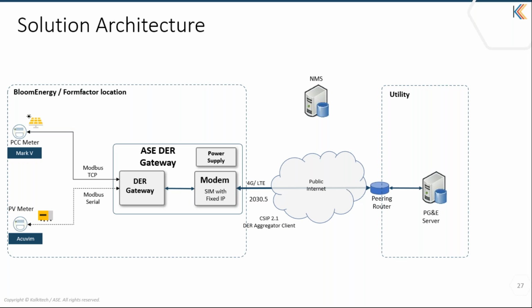And on the other side, we collected the data through Modbus serial. For this data collection mode, we used RS-485, and this meter supports RS-485. Our DER Gateway supports 2 ports. Both can be configured to either RS-232 or RS-485. So we utilized the configuration capability of the DER Gateway and used the second port, that is the default RS-485 port shipped from the factory. So we utilized that connectivity to get the data through Modbus serial.